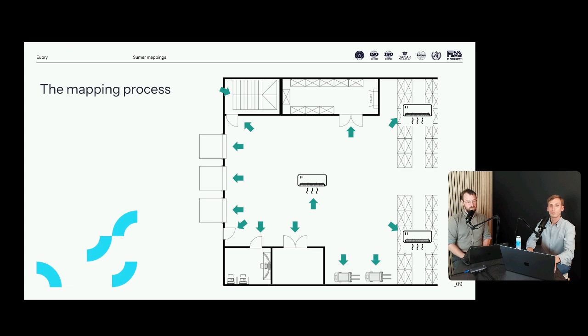Yeah, okay, that's a really good question for Catherine. I think you actually got the point exactly you asked. With new facilities, would you recommend a grid-like approach to start and then repeat with a second placement based on risk? Spot on, Catherine. That's exactly how we do it as well. The grid-like placement is a really good starting point because that's a risk. We monitor for the risk of inhomogeneities, just in the volume that's being used, and then we add on, one might say, the other technical risks that are there with the blowout air from HVAC systems or doors, gates, and so forth on top of that.